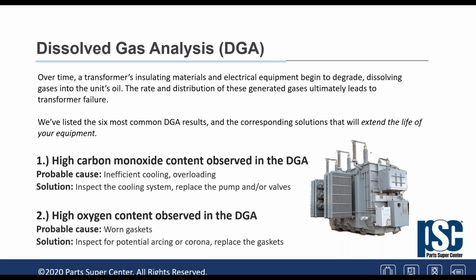But in this case, we're talking about the dissolved gas analysis, which is a much more modern test that the technical people came up with lately. So let's start first with the high carbon monoxide content. Again, the first test that we talked about, the overall oil test, is always recommended at least twice a year, and so is the gas in oil. That's the only way we have to learn what's happening inside the unit without doing any de-energization or going inside the unit and so forth.